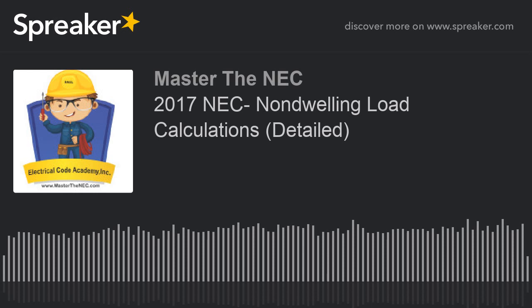If you're following along in your car, don't worry, I'll do it for you. It says track lighting in other than dwellings. So the dwelling unit track lighting is all associated with the general lighting anyway, so you don't have to do anything extra. As well as for guest rooms and guest suites or hotels and motels. And that's what we're talking about. It says an additional load of 150 VA or volt amperes shall be included for every 2 feet of track lighting or fraction thereof.